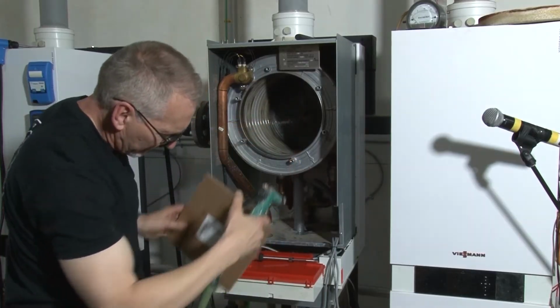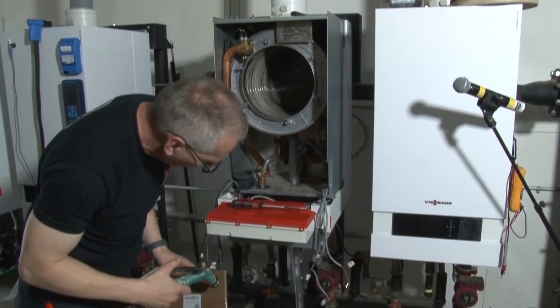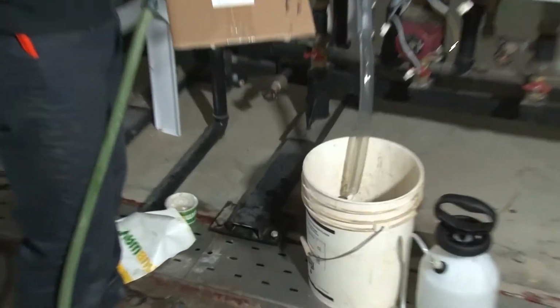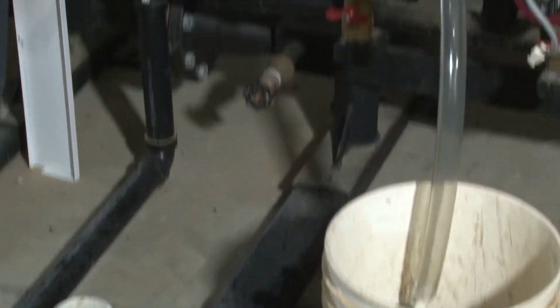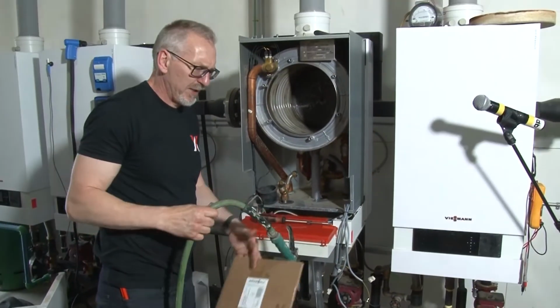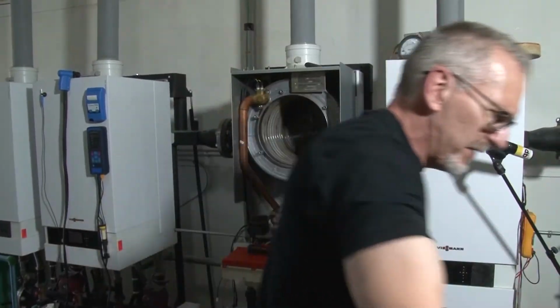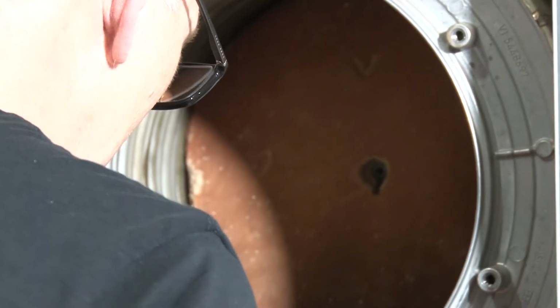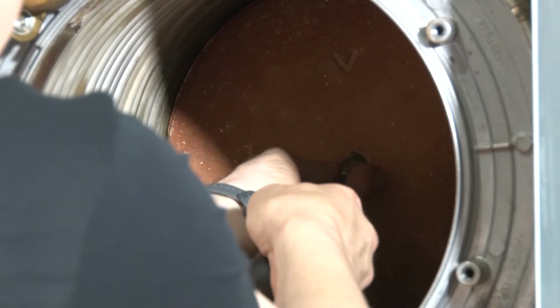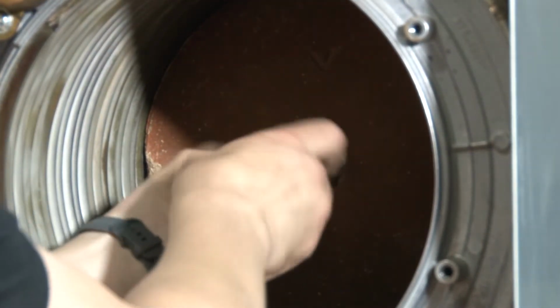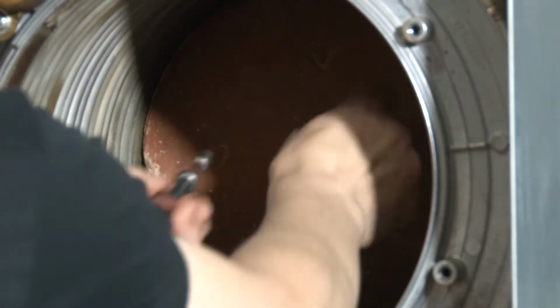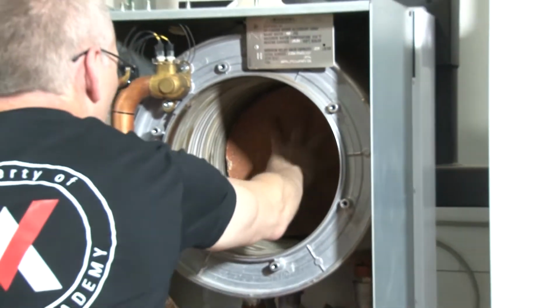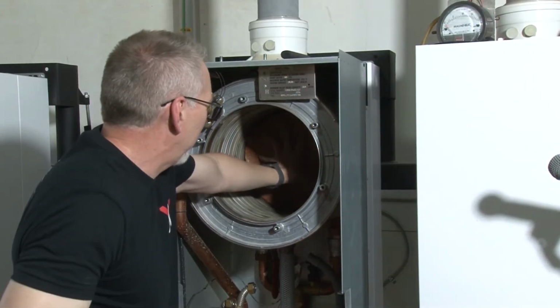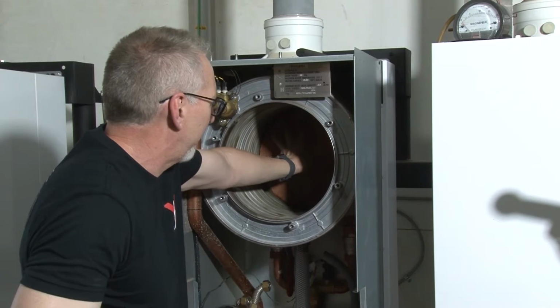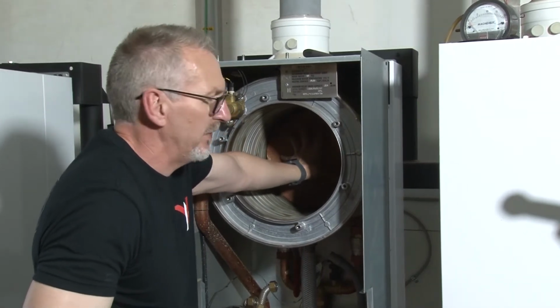So once the pipe is fairly clean, as we see the water's coming out pretty clear there now, I don't have enough debris in there to be a problem for the P-trap, and I've got those flue gas passageways nice and open, so that's basically going to be sufficient. And there we go, refractory's in there. Sometimes a refractory, you put it back in, you'll have a little bit of movement, that's fine. It's basically the whole idea is that it's sealing the back.